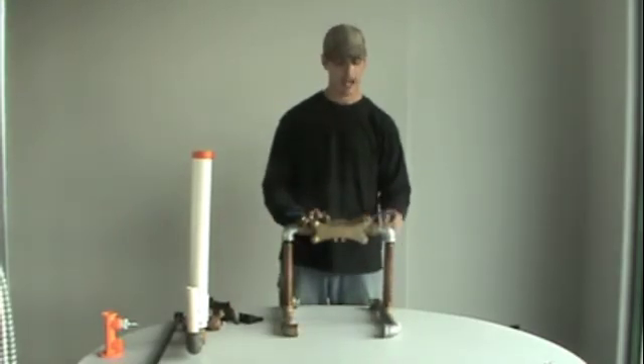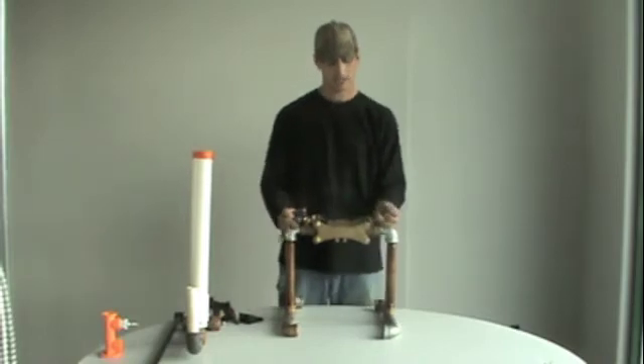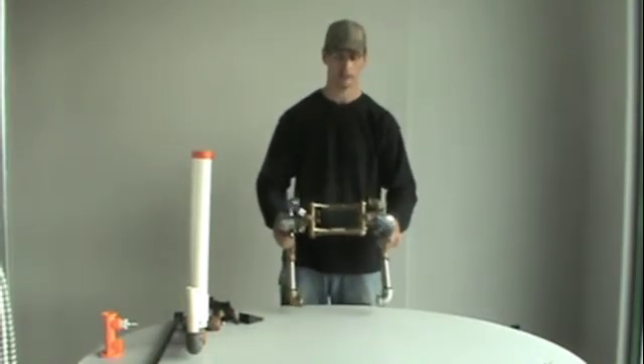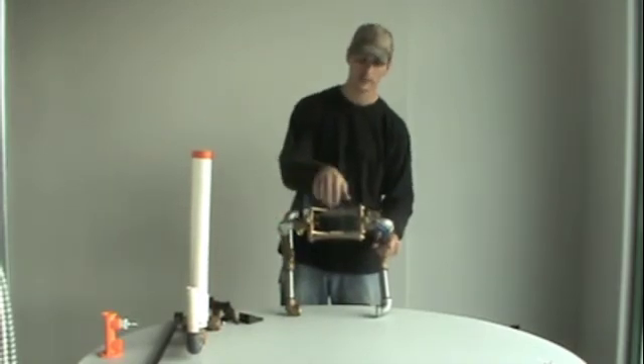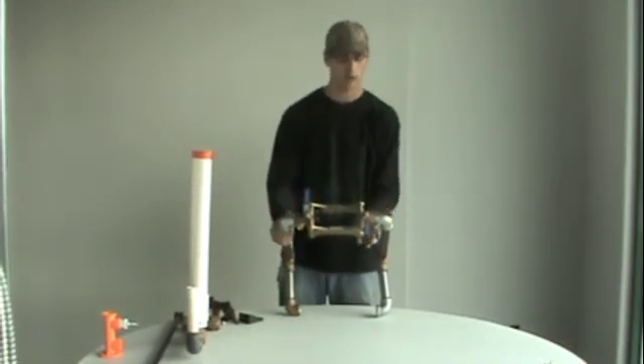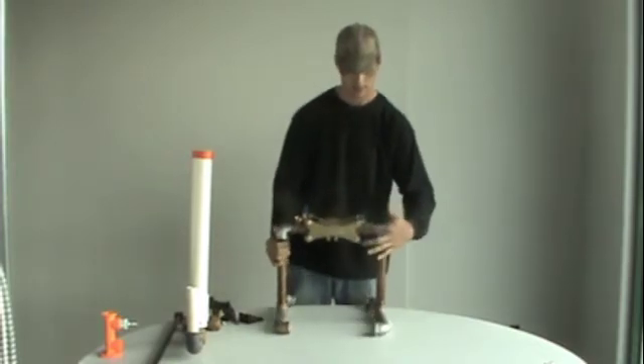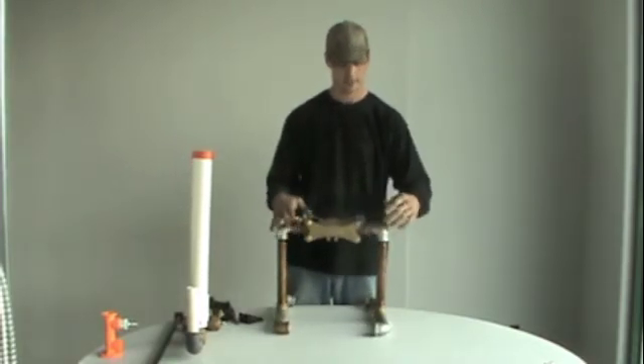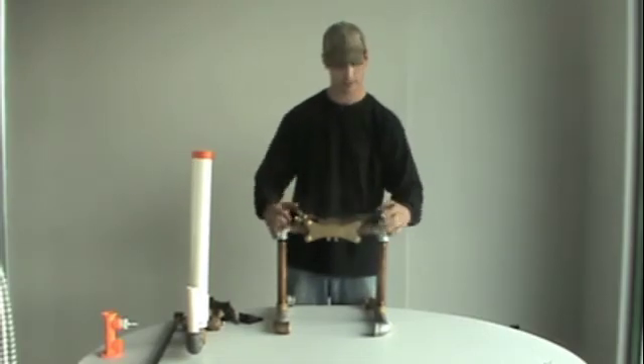Now, after you have completed that, we would like to close these to a 45 degree angle. We do not want to close these all the way. If we close this, water will become trapped here or here, and this is what will freeze and break. And that's essentially what we're wanting to avoid.